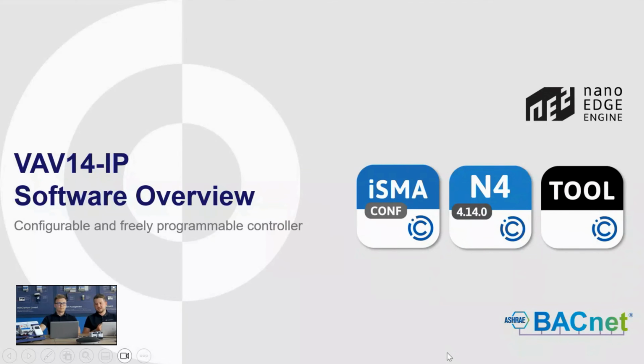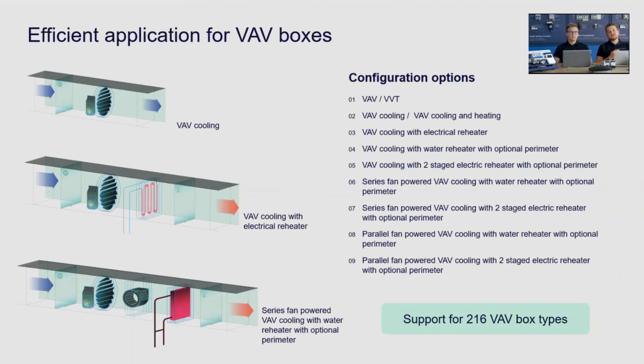So when we look at the application, we have configuration options for the VAV controller for over 200 VAV box types. The controller itself can work as a VAV or a VVT, VAV unit. We support the cooling only or cooling and heating modes. We support the electrical reheater with optional perimeter as well, and a two-stage electric reheater. Overall, there's also an option to set up the fans in parallel or series, which altogether gives you the combination of over 200 VAV boxes.